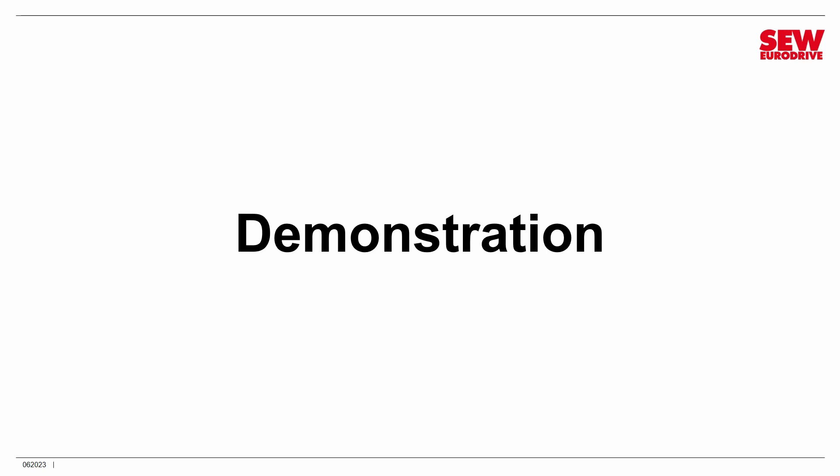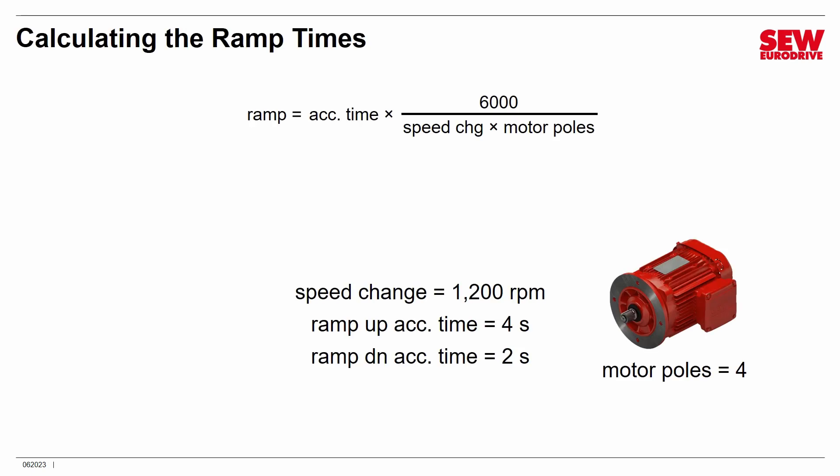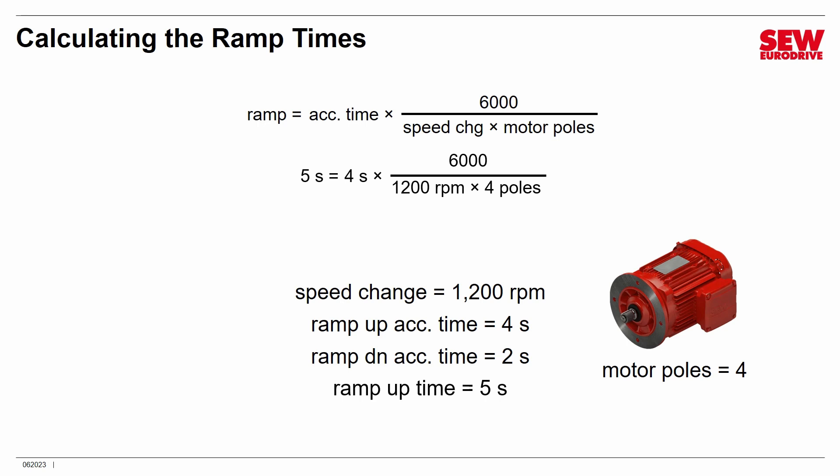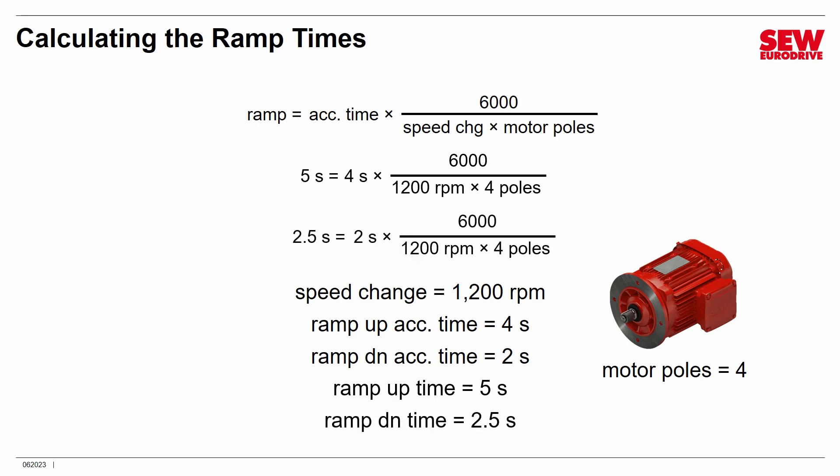Let me demonstrate the solution. First, calculate the ramp times. Using the equation introduced earlier: for a 1,200 RPM speed change with a 4-second up acceleration time and a 4-pole motor, the formula gives: 4 seconds × 6,000 ÷ (1,200 RPM × 4 poles) = 5 second ramp time. For the down ramp with 2 seconds: 2 × 6,000 ÷ (1,200 × 4) = 2.5 second ramp time. So we need to program 5 seconds and 2.5 seconds into the right parameters to achieve the desired acceleration and deceleration for a 1,200 RPM speed change.